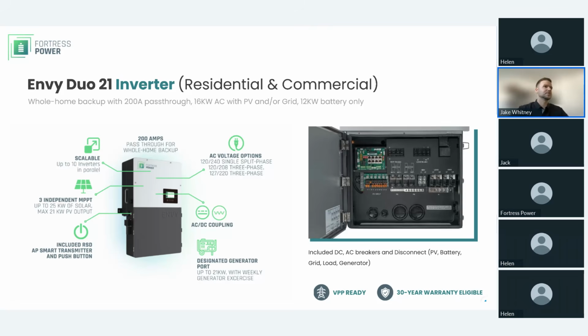So what comes built inside this inverter? 1, it comes with a built-in 200 amp pass-through. It can do a 16 kilowatt AC with the PV and or grid, and then 12 kilowatt for battery only. You can scale up to 10 of these inverters in parallel if the application of the job requires more output or more backup. Inside here, there is 3 independent MPPTs. Now, a part of those MPPTs, there's a total of 5 inputs for your PV array, which will allow you to have 25 kilowatt of solar and a max 21 kilowatt of PV output. This is massive because this will allow you to use one inverter if the PV array is large.